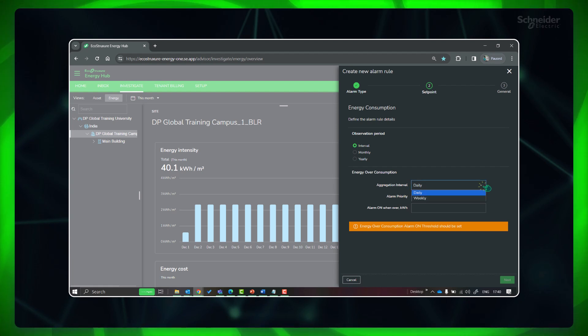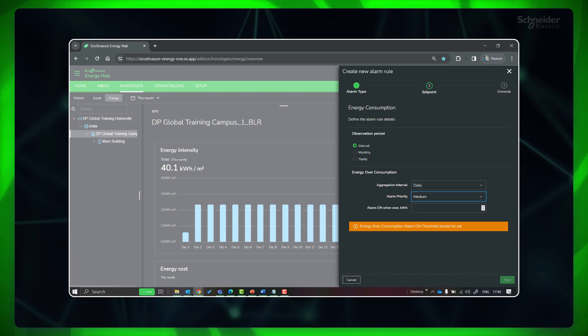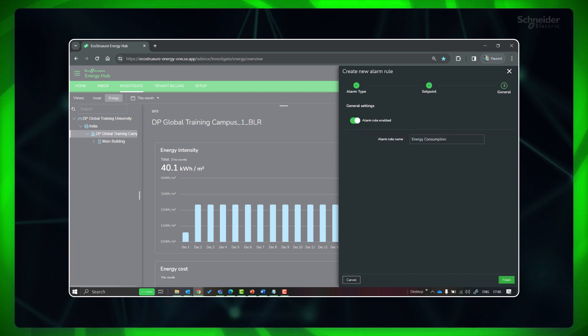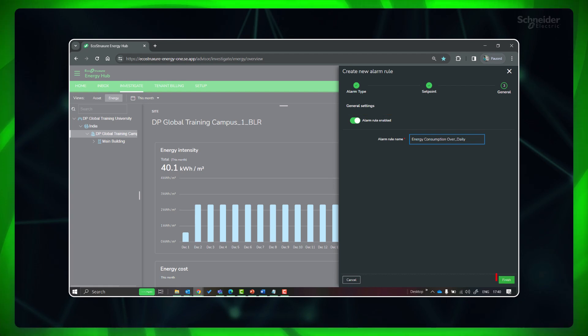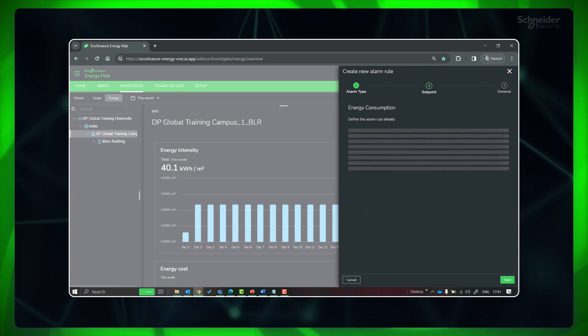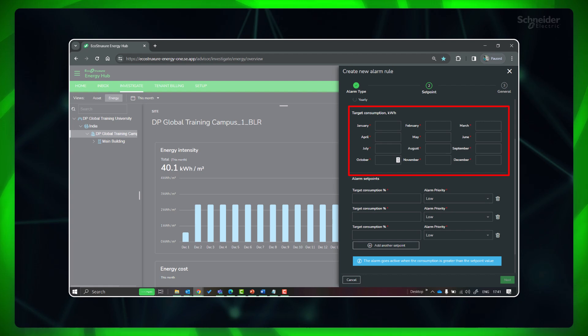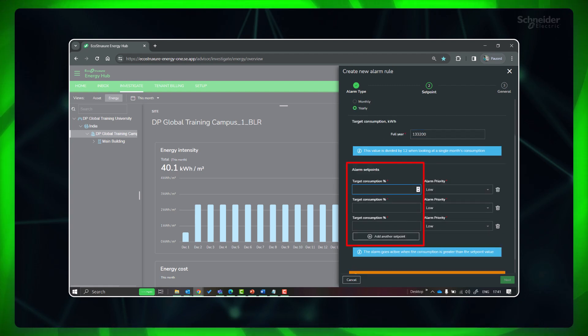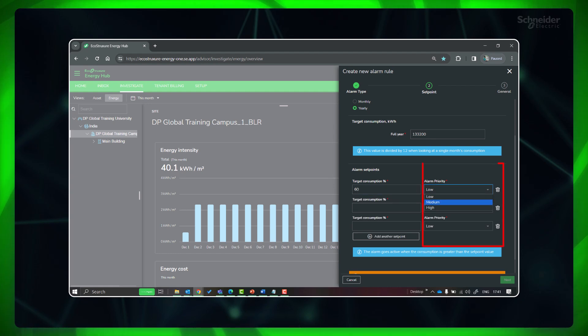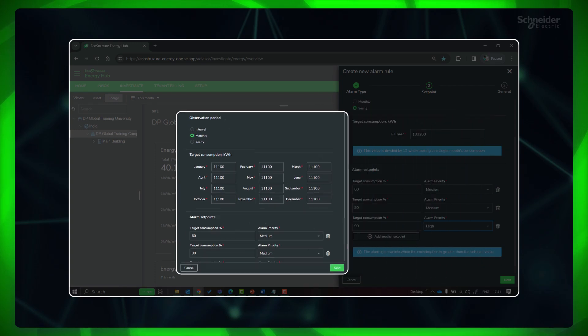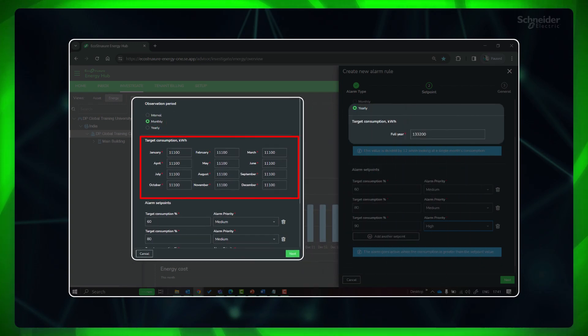Select the interval — for example, Daily. Set the priority to Medium. Provide the daily threshold at which you need this alarm to trigger. Give the rule a name, then toggle the switch to on or off to enable or disable the alarm, and click Finish. Similarly, you can set a monthly or yearly overconsumption alarm, providing either separate monthly targets or a single yearly target. Provide the thresholds in percentage of target where you want to generate the alarms and set the priority. If you provide a yearly target, it will be equally divided into monthly targets automatically.